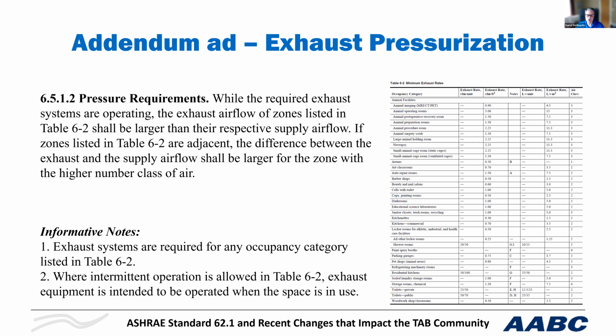Many designers perhaps do not realize that the difference between the airflow supplied and the airflow exhausted actually creates the pressurization. This is known as the pressurization flow. So simply put, if you have more air exhausted out of a space than supplied to the space, then you have a negative pressure space. But let's take into consideration that we have a lot of exhaust fans now, especially in restrooms and other spaces, that are tied to light switches or occupancy sensors. Well, that doesn't turn on until someone occupies a space.